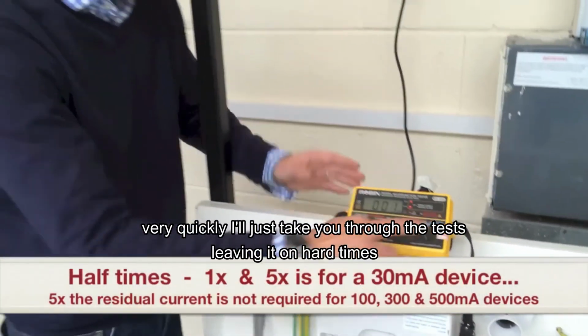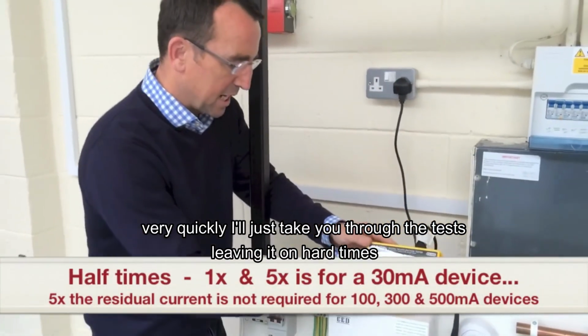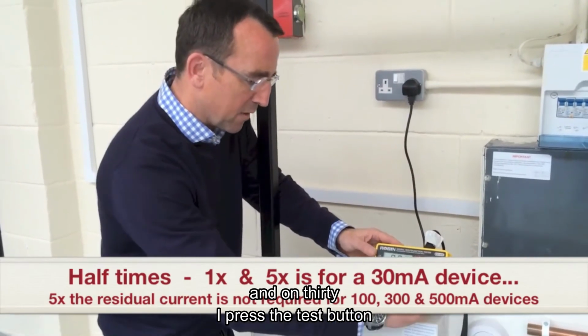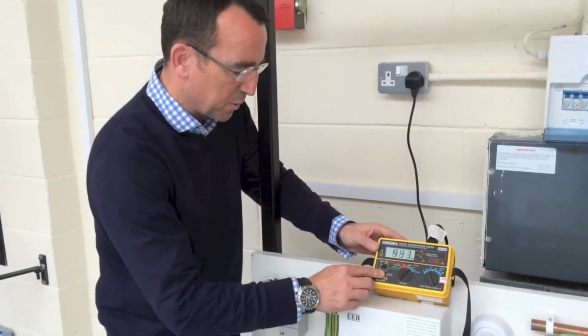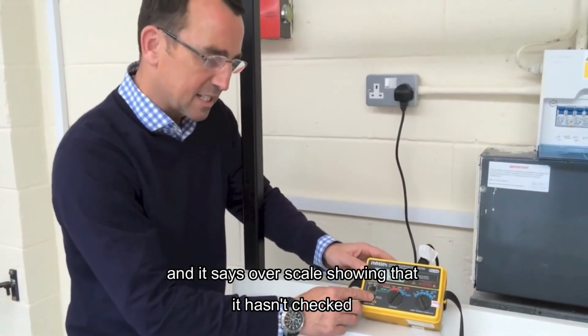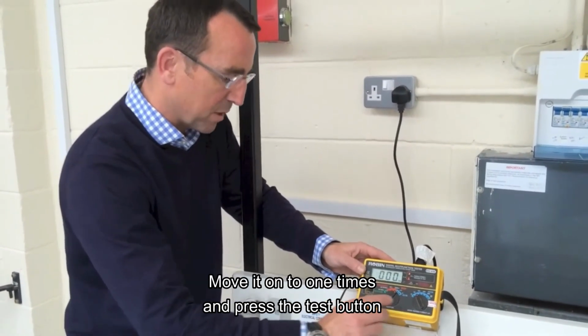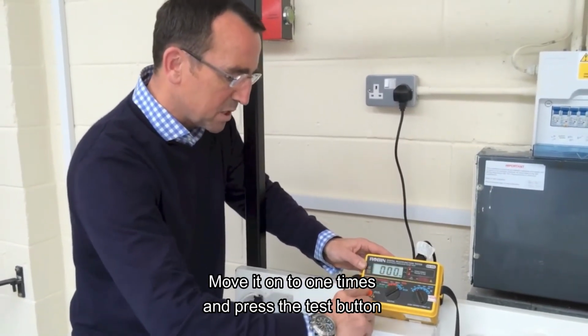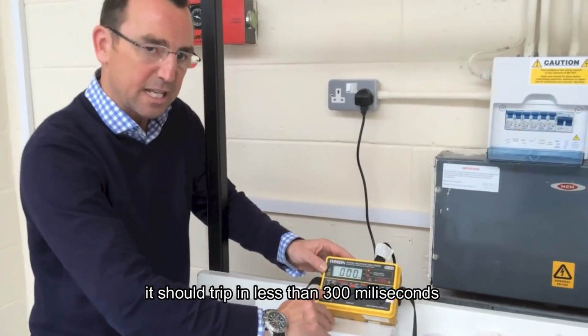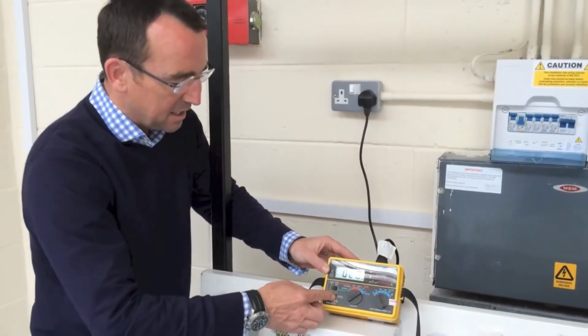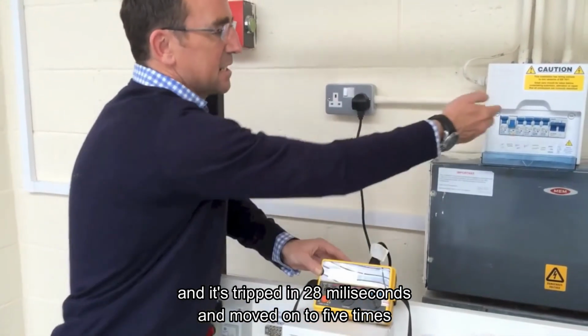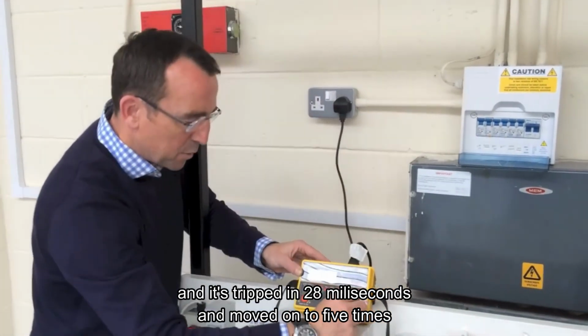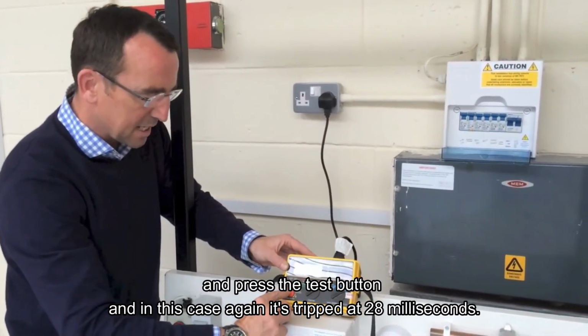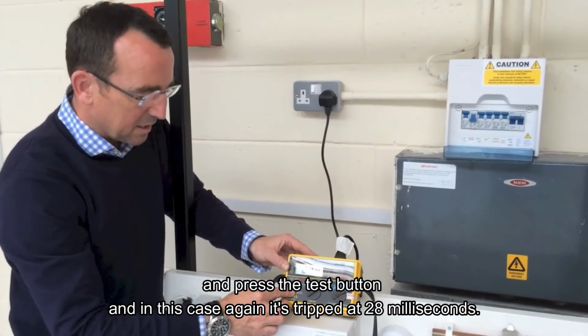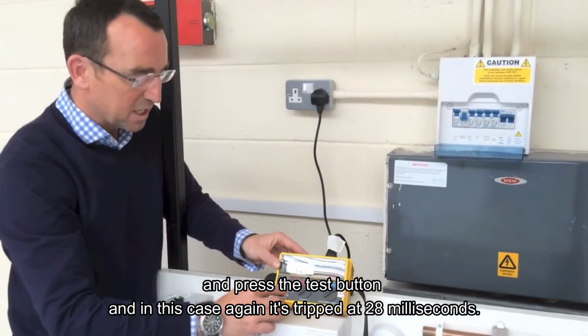Quickly, I will just take you through the test. Leaving it on half times, on 30, I press the test button, and it says overscale, showing that it hasn't tripped. Move it to 1 times and press the test button. It should trip in less than 300 milliseconds, and it tripped in 28 milliseconds. Move on to 5 times and press the test button, and in this case, again it tripped at 28 milliseconds.